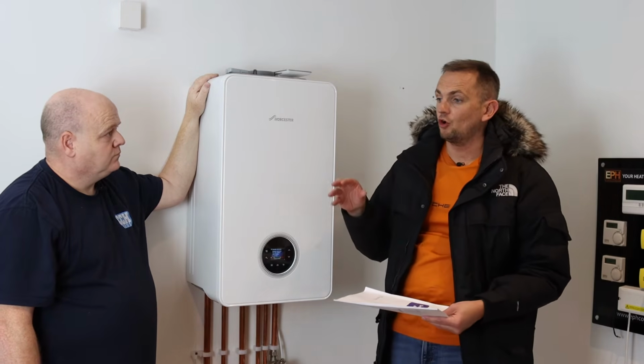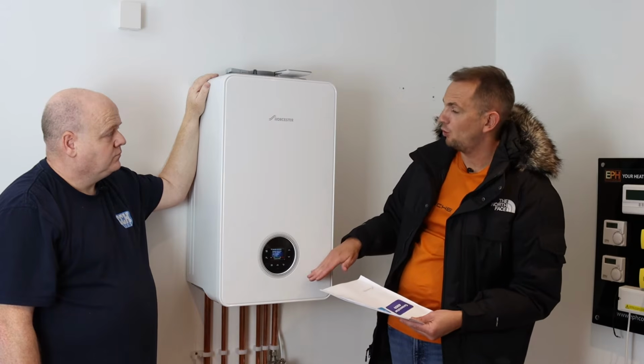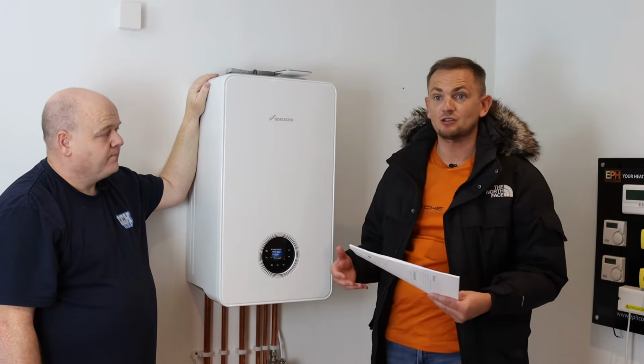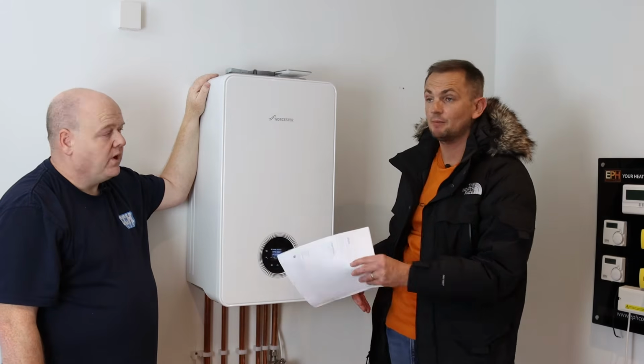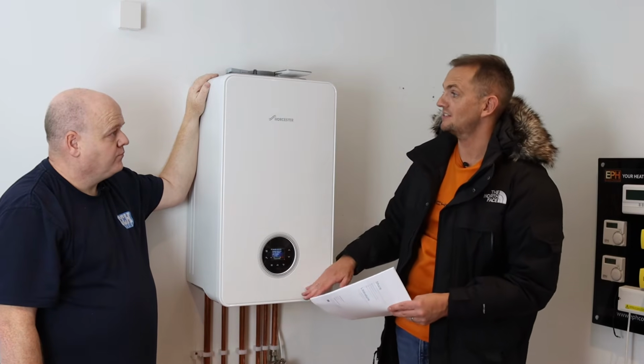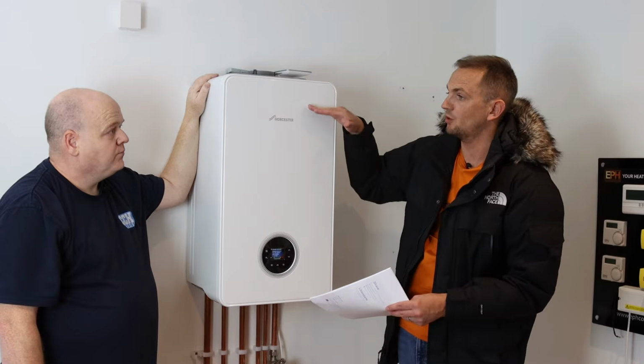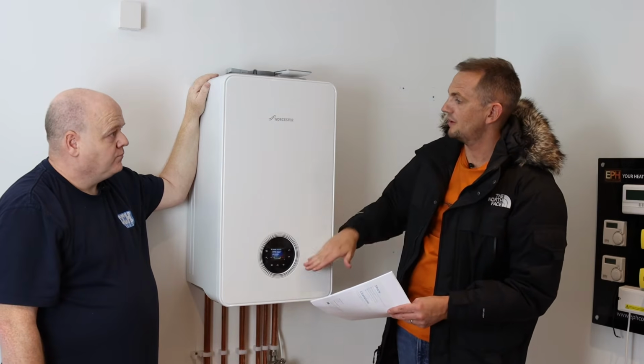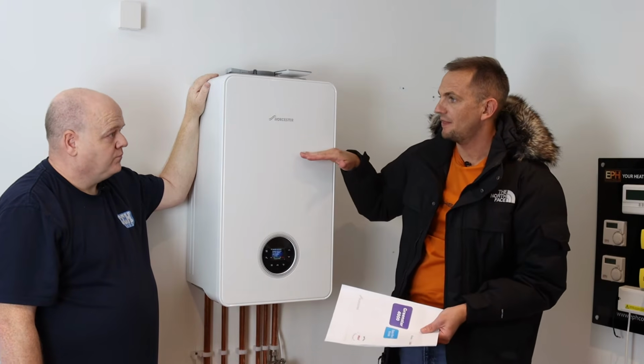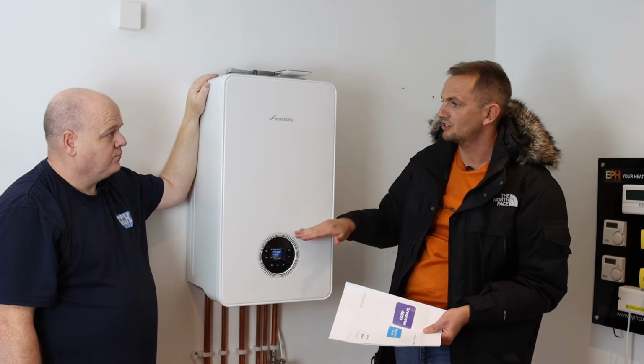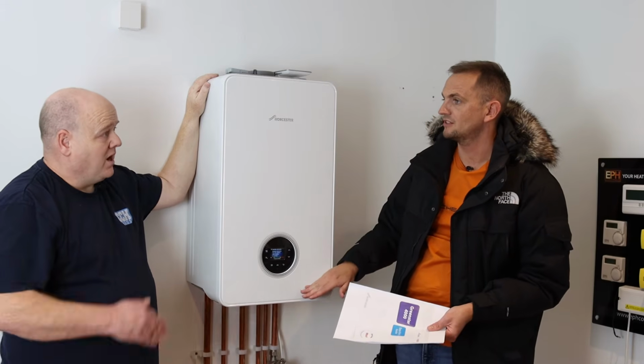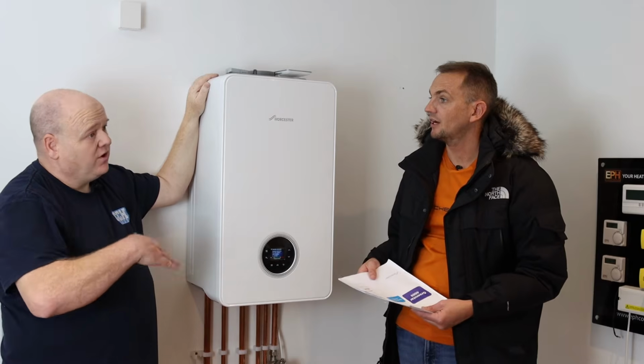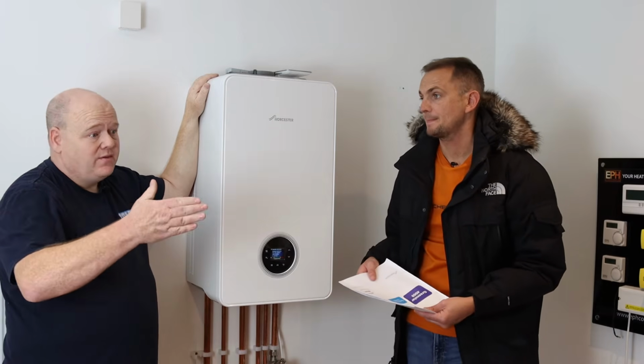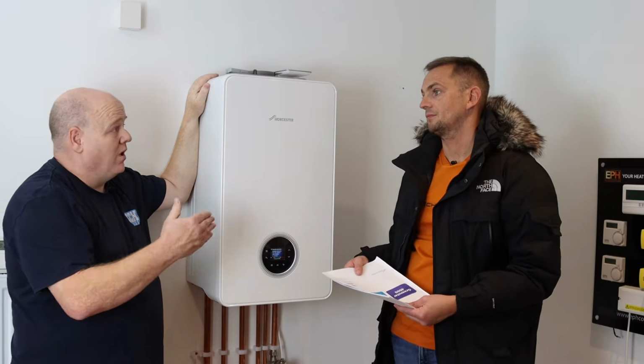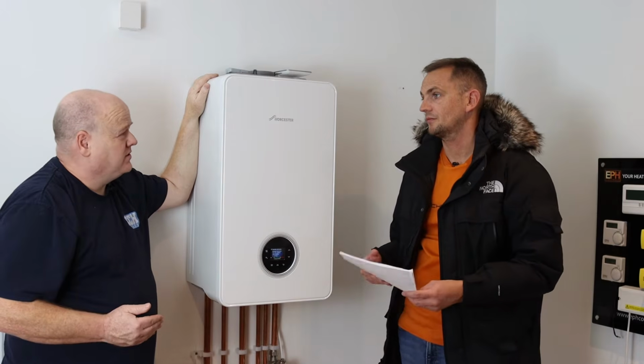What you were mentioning before, the range rating element is what the engineer can do as a further setup. It's not something a customer can do on here, but what an engineer can do as a further setup is set its maximum kilowatts you want it to go to. So you might set it at 20, let's say, and then it will automatically make its own decision from that position you've set it. And you can set it lower than that if you wanted to. So if you go to a house and it's a smaller house, then you can set that all the way down to whatever you want it to be, down to 13 kilowatts, I think it is.